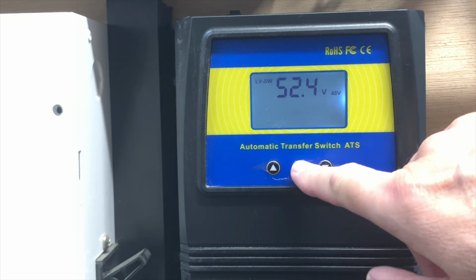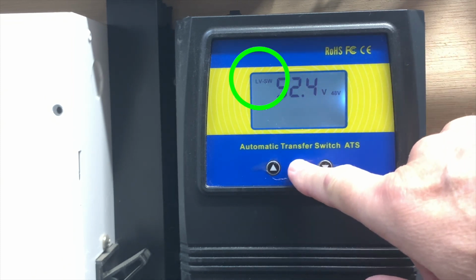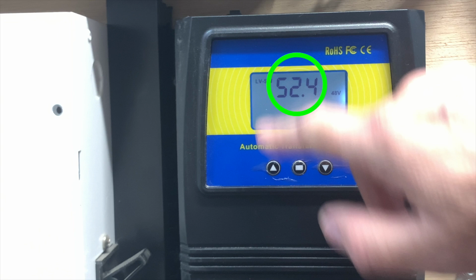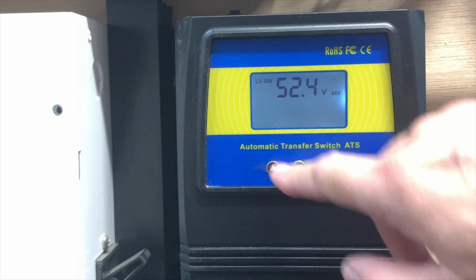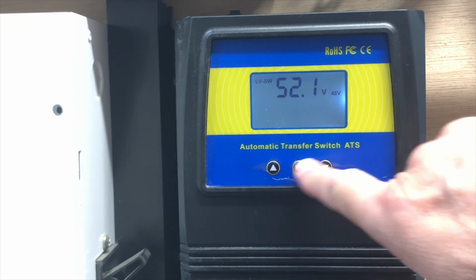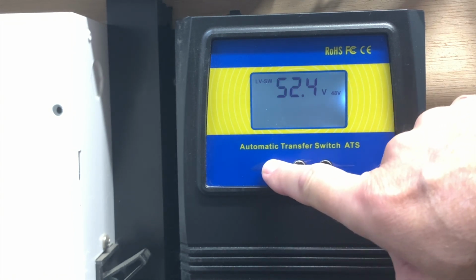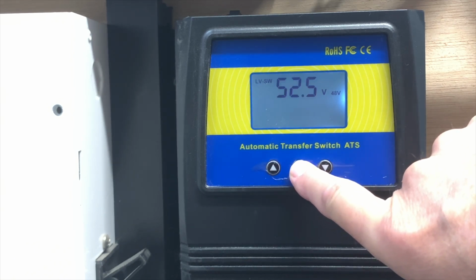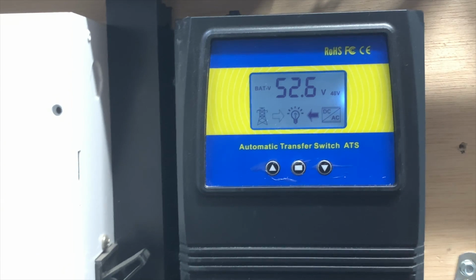We press this center button and we're now on the low voltage switch page. When the battery falls below this voltage, we will switch from inverter to grid power. Use the up and down arrows to change this voltage in increments of 1/10 of a volt. To save the setting, you hold the center button until it jumps back to the home page. So what I'm going to do to make this thing drop in voltage is I'm going to turn on a little space heater I have over here. And watch. There we go. And it just switched over to grid power.